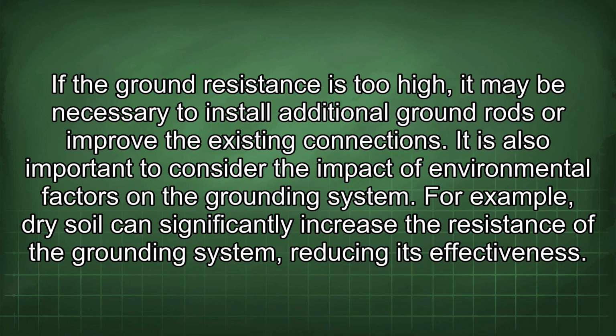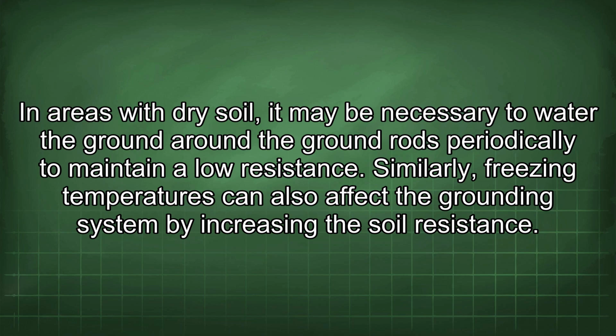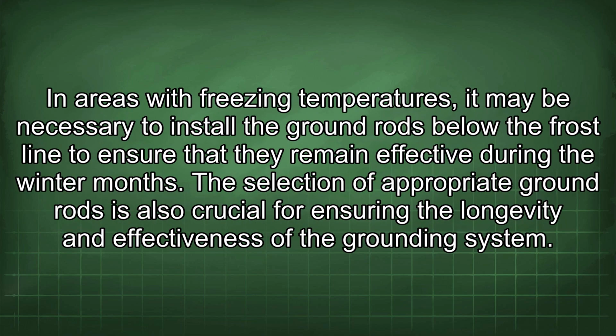It is also important to consider the impact of environmental factors on the grounding system. For example, dry soil can significantly increase the resistance of the grounding system, reducing its effectiveness. In areas with dry soil, it may be necessary to water the ground around the ground rods periodically to maintain a low resistance. Similarly, freezing temperatures can also affect the grounding system by increasing the soil resistance. In areas with freezing temperatures, it may be necessary to install the ground rods below the frost line to ensure that they remain effective during the winter months.